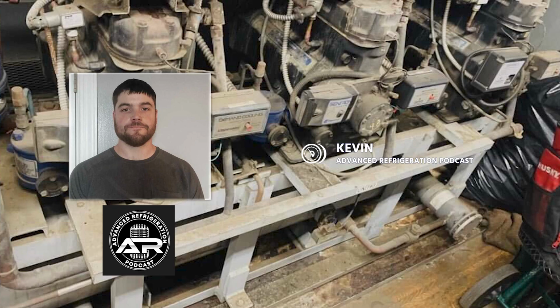Yeah, we see this a lot in Florida for all the reasons that you mentioned, other than all the snow stuff, because we don't know what that is. But we use it a lot for reheat for dehumidification as well. So when you have a need to dehumidify, but you don't have a need for comfort cooling, then you can cool the air, drop the moisture, and then reheat it using that excess heat that you had from the rack refrigeration system. Yeah, I wish we had more reheat around here. We're not allowed to have that.